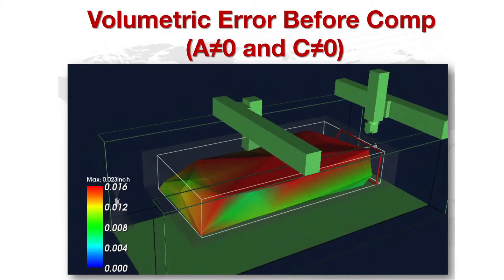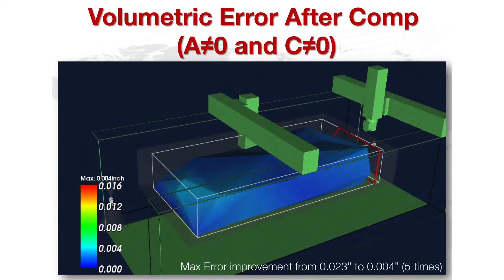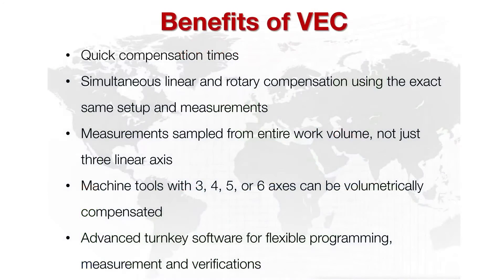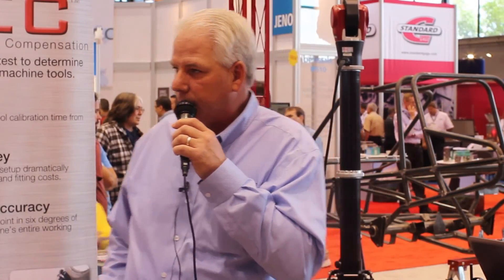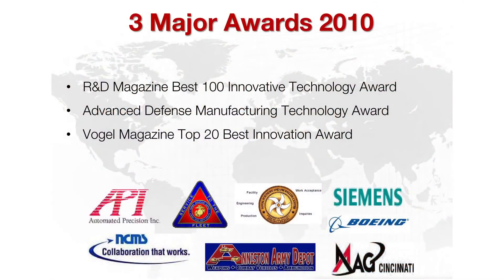Here we show a 3D error map of errors on a machine showing a 23-thousandths max error before calibration, reduced to 4 thousandths after calibration. Benefits of VEC include quick compensation times; we can simultaneously measure the rotaries and linears at the same time across up to six axes. We have a full turnkey software solution for generating programs and implementing compensation. API was awarded three awards in 2010 for VEC: the R&D Magazine Best 100 Innovative Technology Award, Advanced Defense Manufacturing Technology Award, and the Vogel Magazine Top 20 Best Innovation Award.